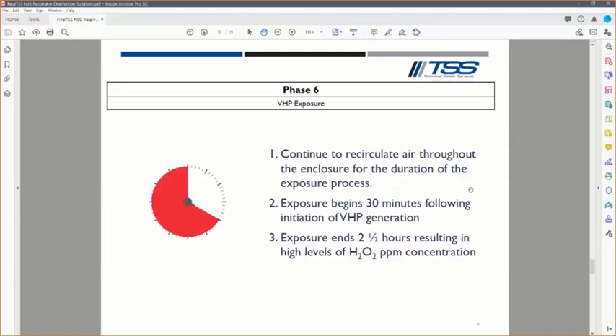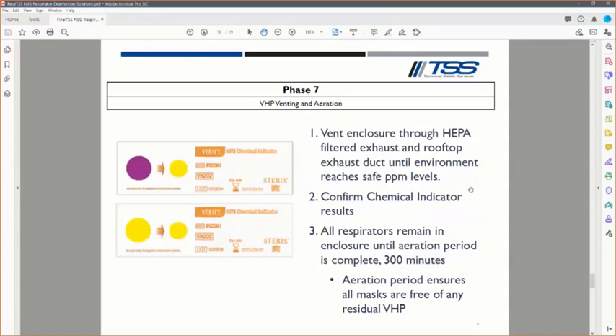Following very defined exposure periods, 30 minutes of dwell after the generation and 2.5 hours of exposure even after that, then we'll begin venting until it gets back down to the 1 ppm OSHA limit in order to enter the unit. Following that, we also have a 300-minute minimum aeration period at the 1 ppm or low result. This is based on guidance of residue on the masks and how long any VHP residue may be present. In our experience, we have not found that even about 30 minutes later, any of the masks have residue, but we follow the 300-minute guidance.